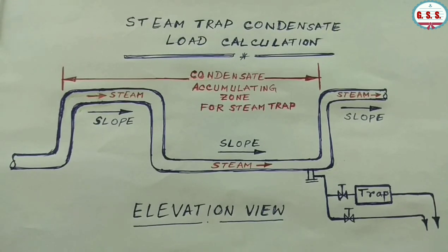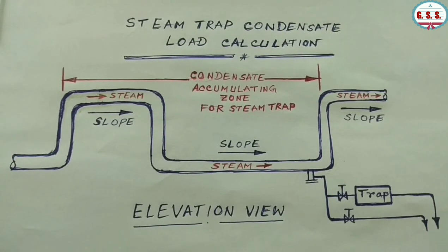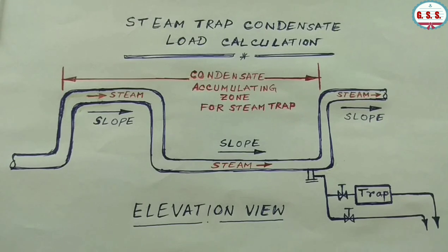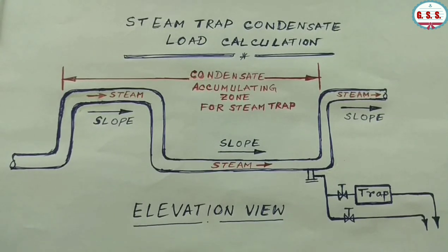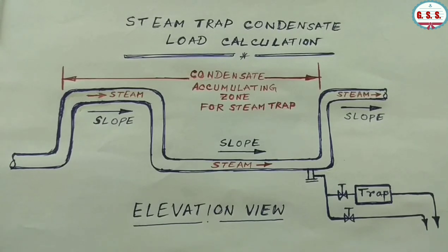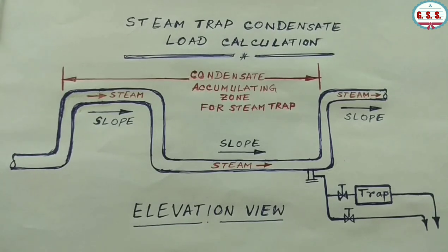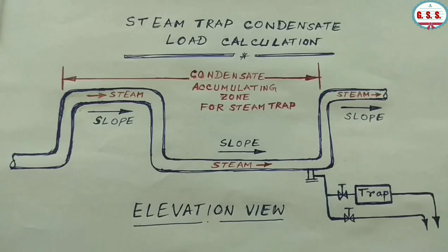This piping configuration shows the steam line in vertical and horizontal planes. If the entire steam line is in the horizontal plane with horizontal loops, then traps should be provided at about 100 to 120 meters apart and the condensate load is to be calculated for that length of steam line.